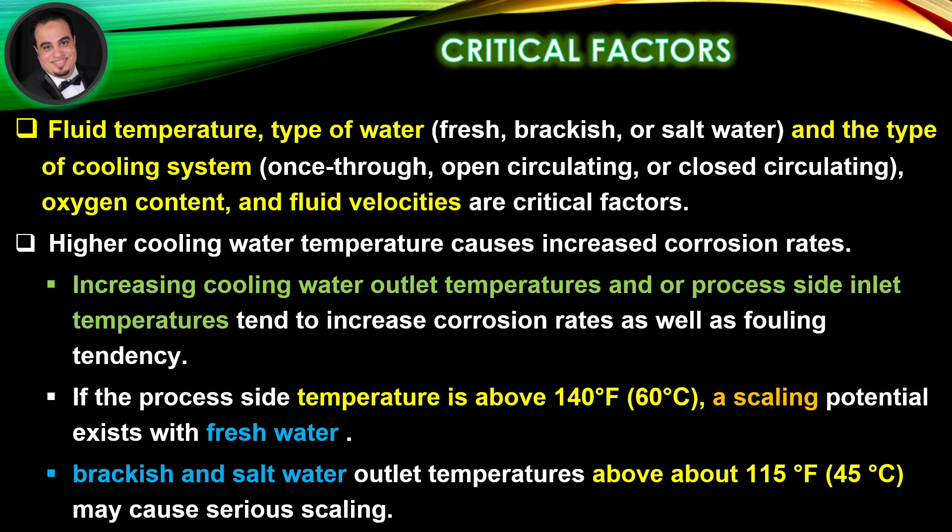Higher cooling water temperature causes increased corrosion rates. Increasing cooling water outlet temperatures and process side inlet temperatures tend to increase corrosion rates as well as fouling tendency. If the process side temperature is above 140 degrees Fahrenheit, a scaling potential exists.